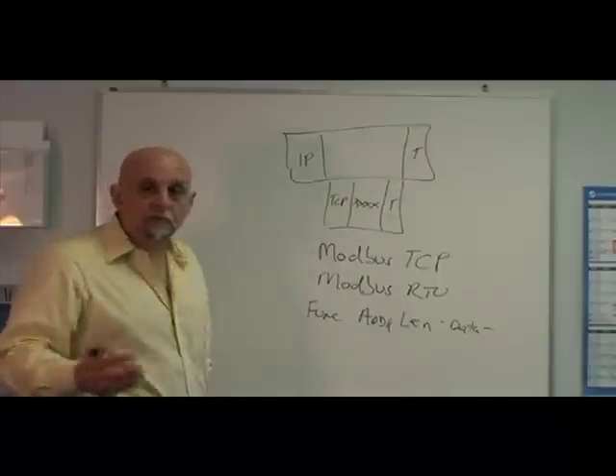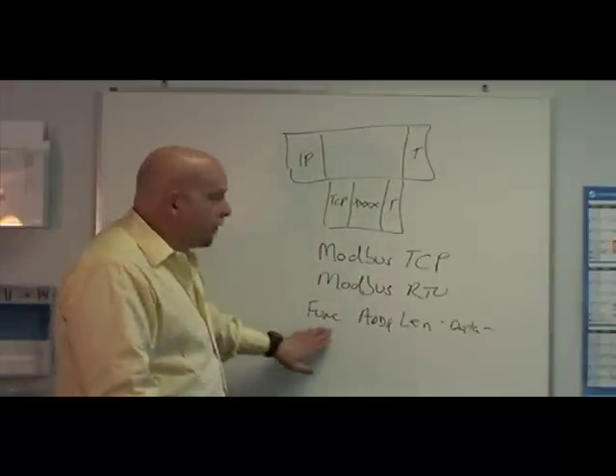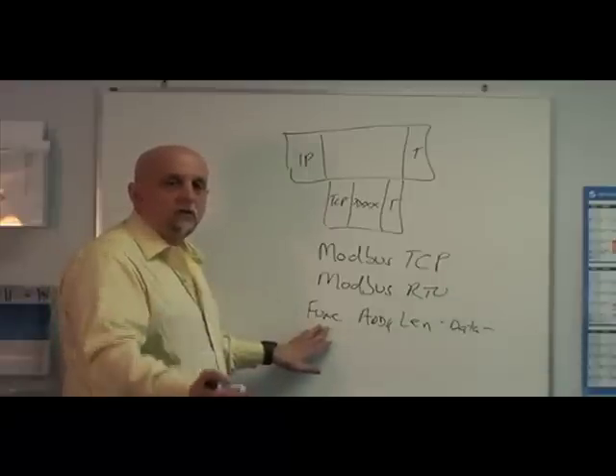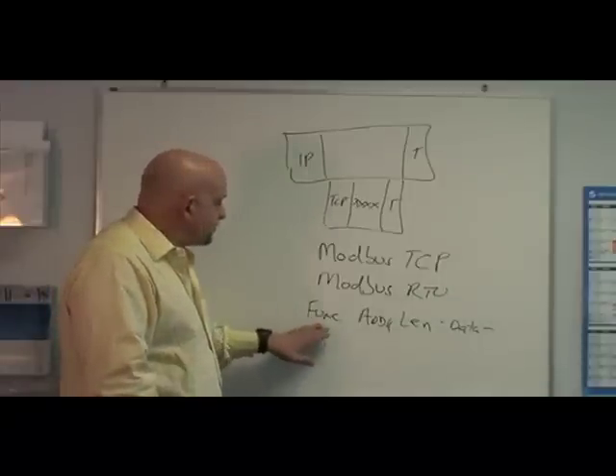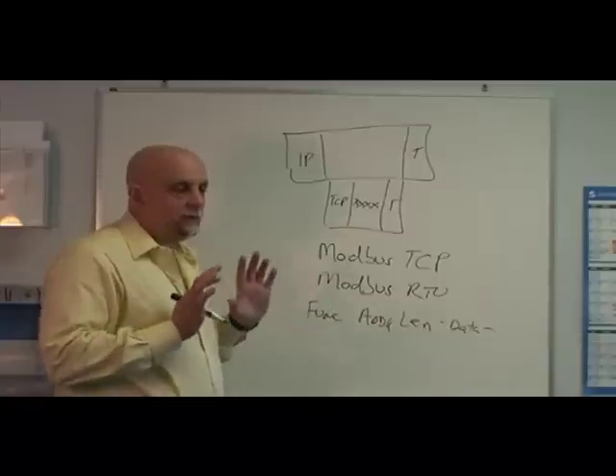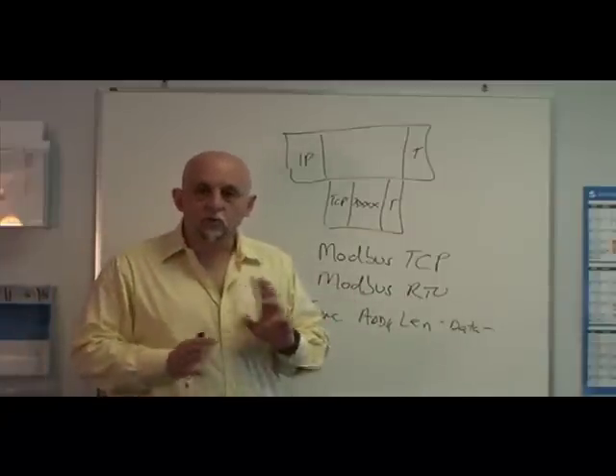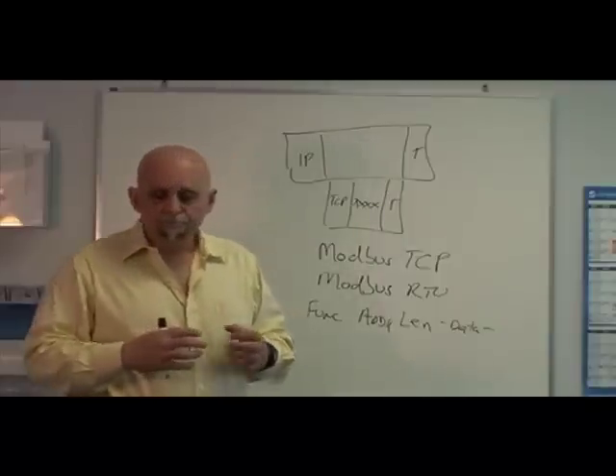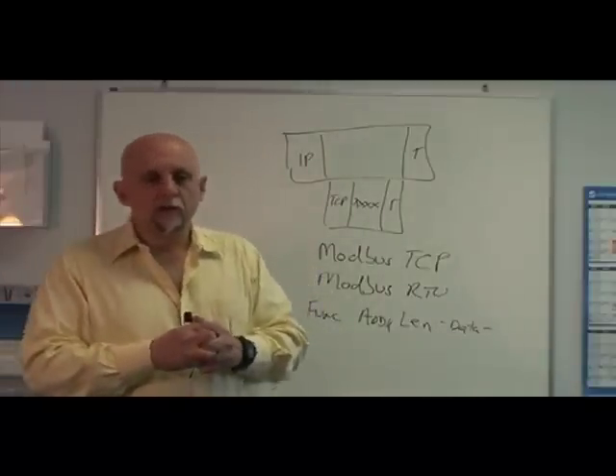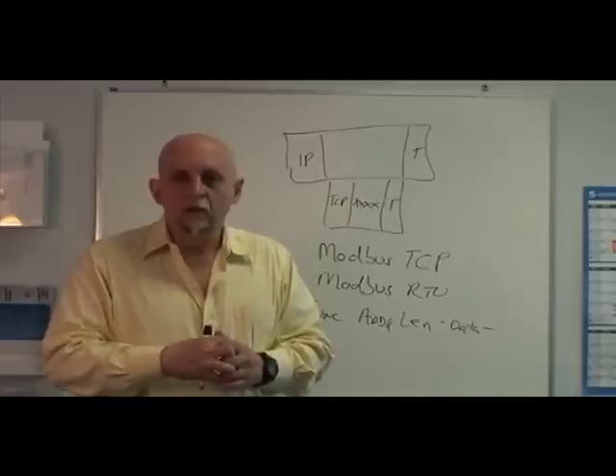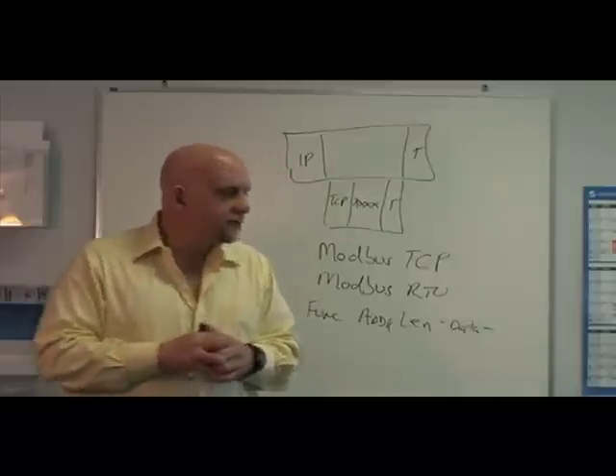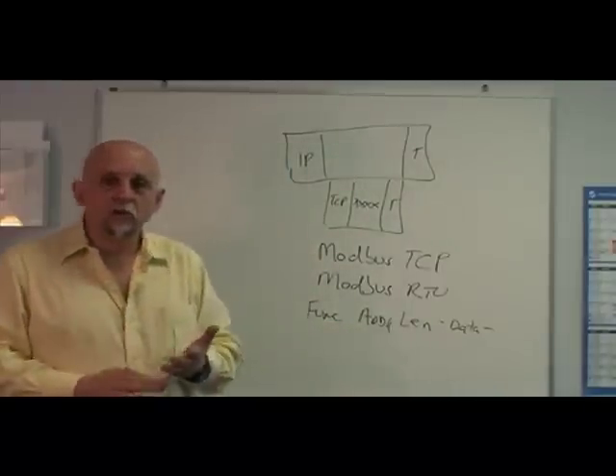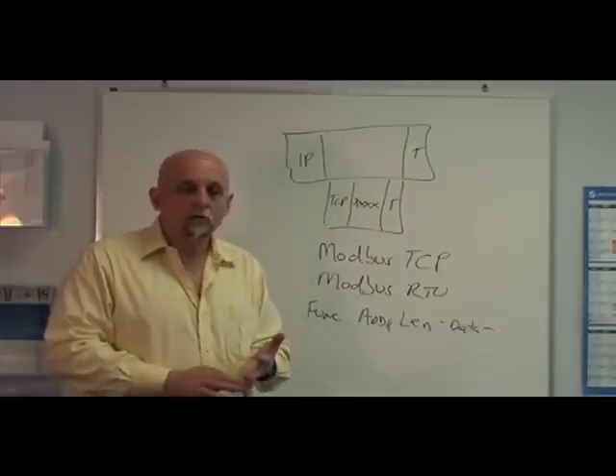The function code says I am reading registers, I'm writing registers, I'm reading coils, I'm writing coils, and there's different sets of registers and coils you can have. This goes back to the old days when they actually had real analog inputs and then you had inputs that were in memory and such and stuff like that. So function code, there are some function codes to read input registers, other function codes to read holding registers.